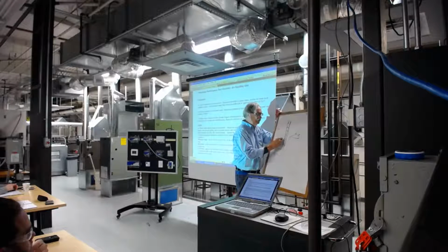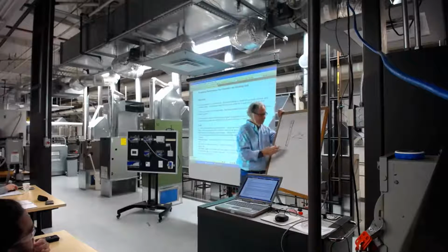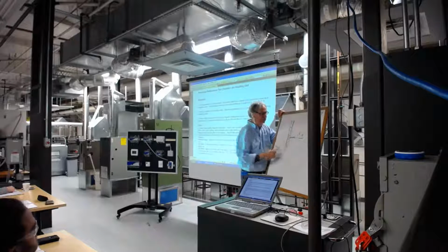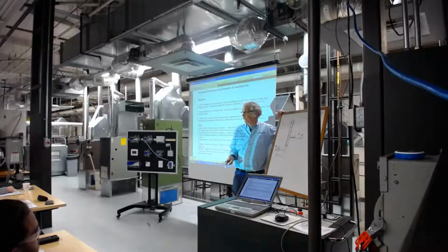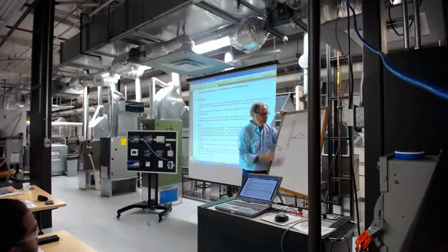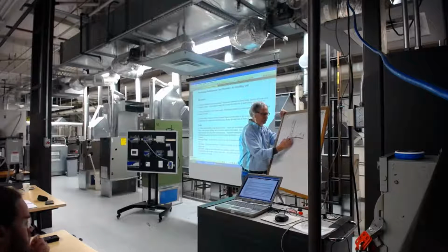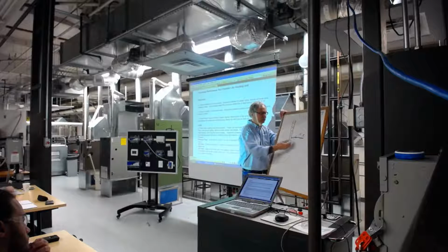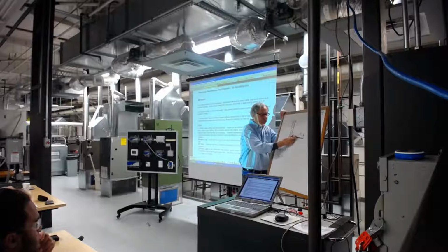So what's happening here is the surface of this coil is approximately, given an approach, 45 degrees, and then this surface is approximately going to be 55 degrees. We'll assume we're in Florida, so we've got not only dry bulb but wet bulb, humidity. We'll assume we're in the summer with a heavy latent load, a lot of humidity, and sensible. So the air hits this right here, and you begin to sensibly cool. You're starting to drop the dry bulb temperature down.